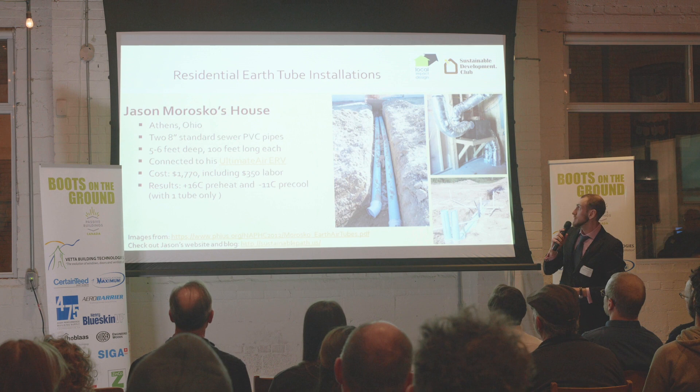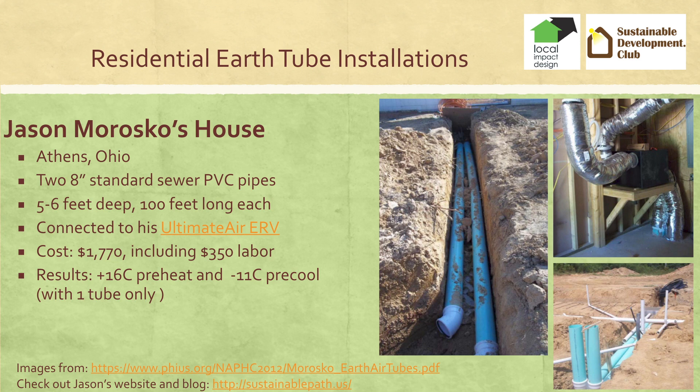Here are some examples. Jason Morosko's is a very typical project: two pipes bought at Home Depot or Lowe's, buried about five to six feet deep, 100 feet long, connected to his Ultimate Air ERV. It cost him $1,700, including his own labor priced at $350 for about four hours. The results are plus 16 degrees Celsius preheat in the winter and minus 11 pre-cool, and he was operating only one earth tube out of two.